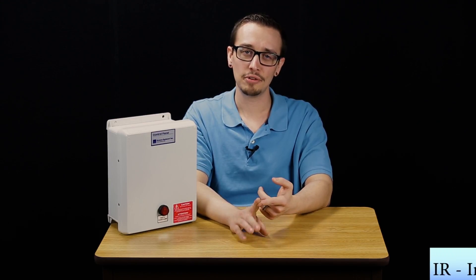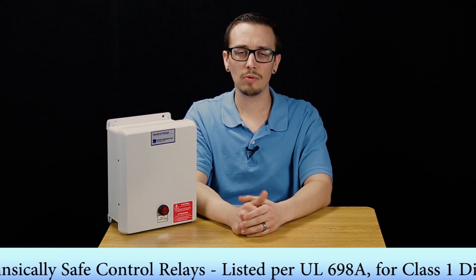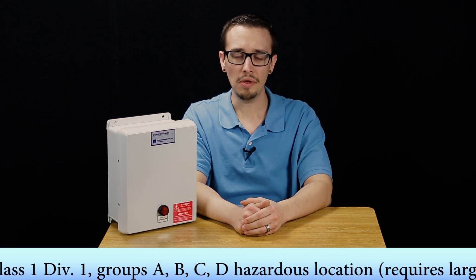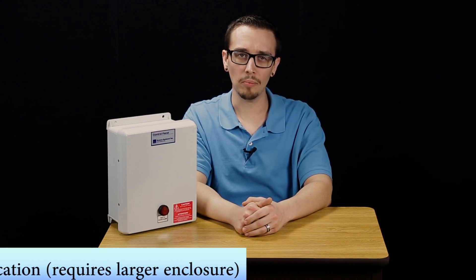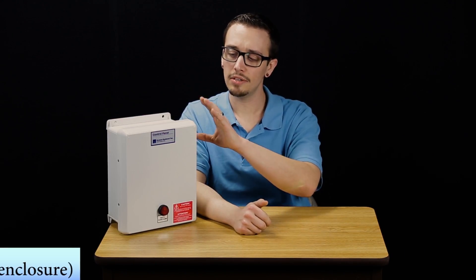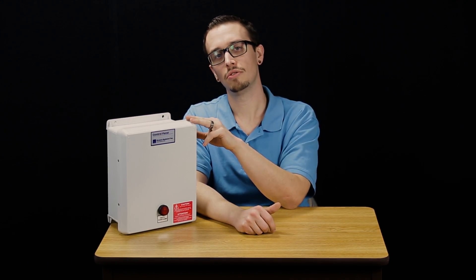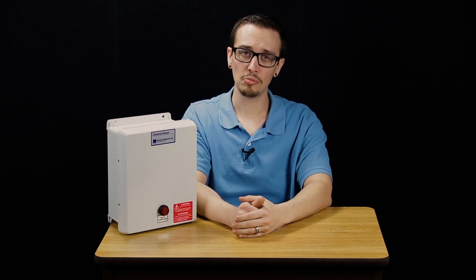We have the intrinsically safe relay or IR as it's called out in the part number. And what this is, gets the panel set up with intrinsically safe relays for a class one division one hazardous environment pump. It is notable, though, that if that particular upgrade doesn't fit in this enclosure, you will receive that panel with a slightly larger enclosure. So do be aware of that.